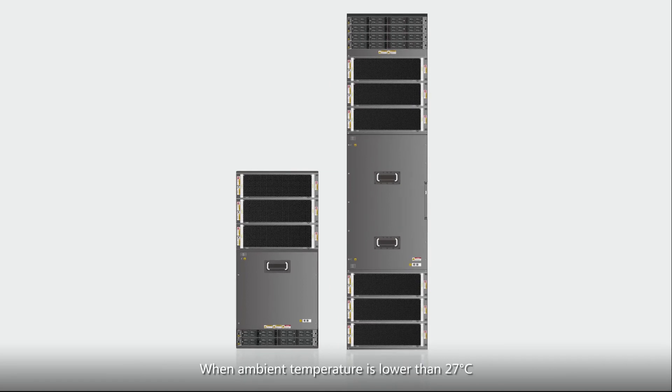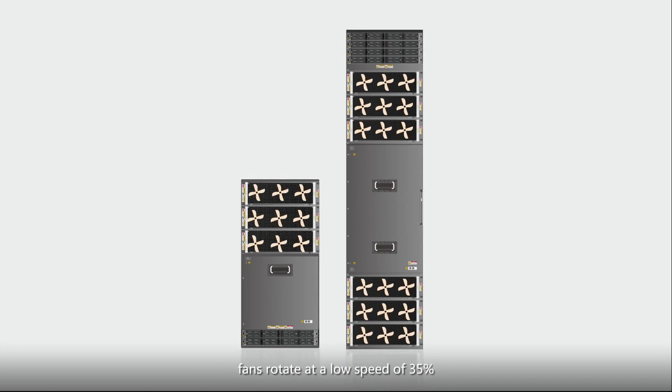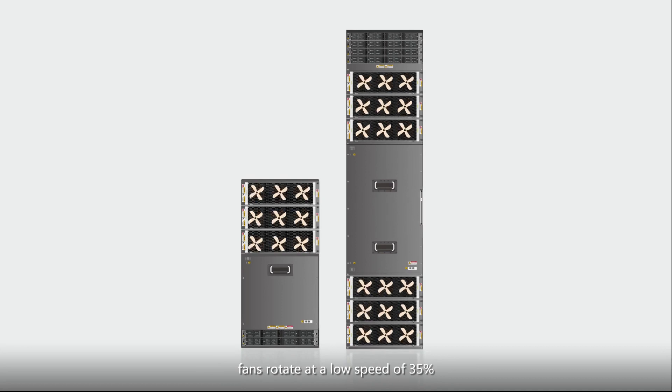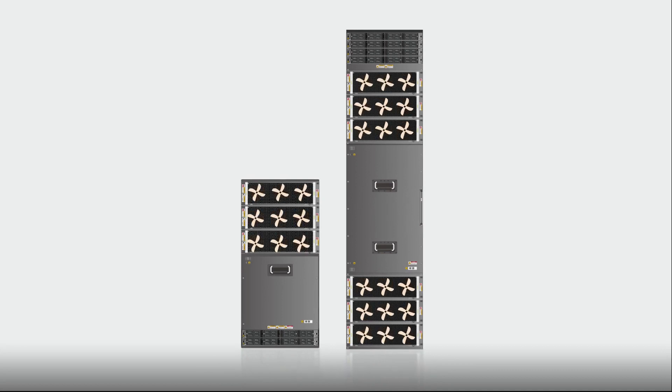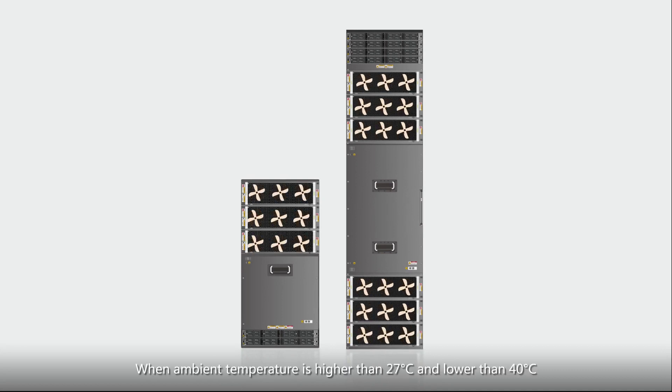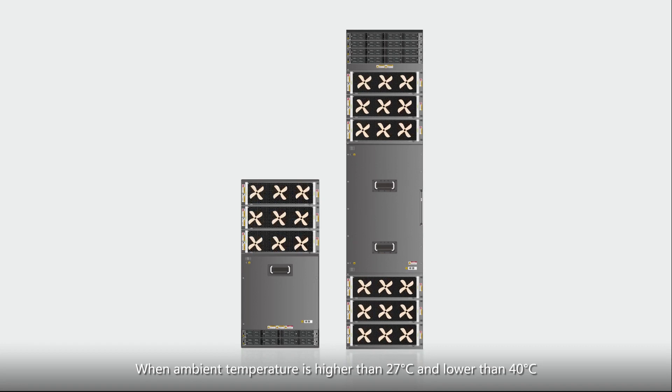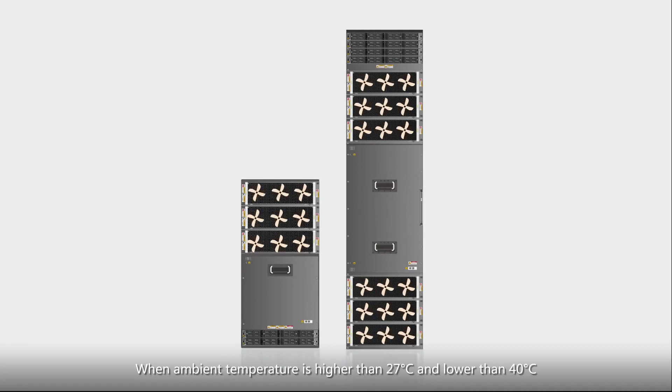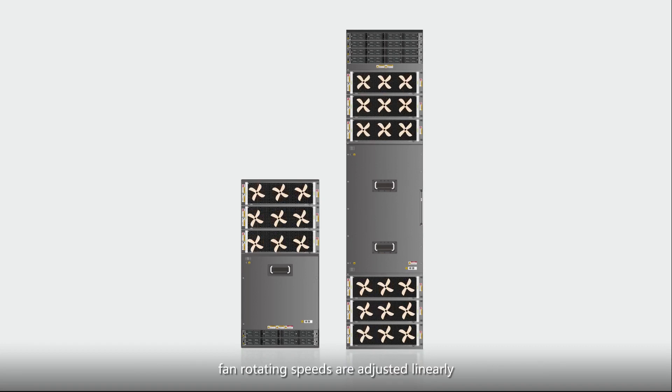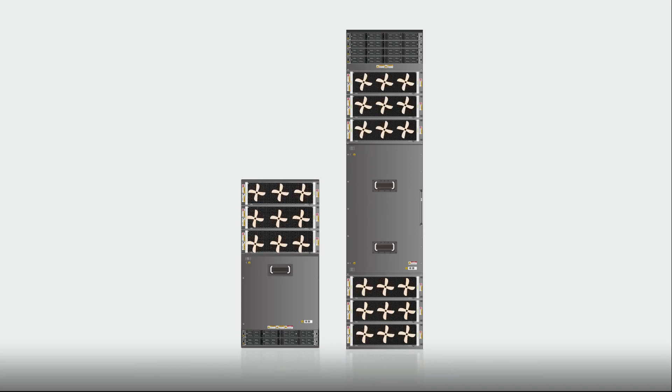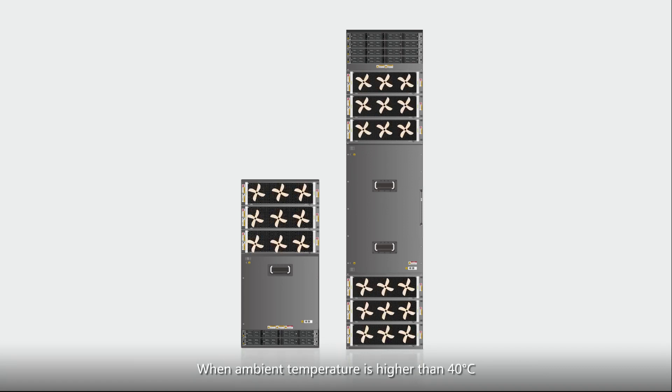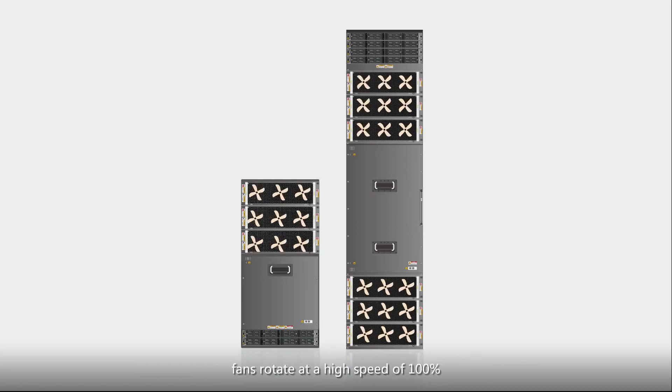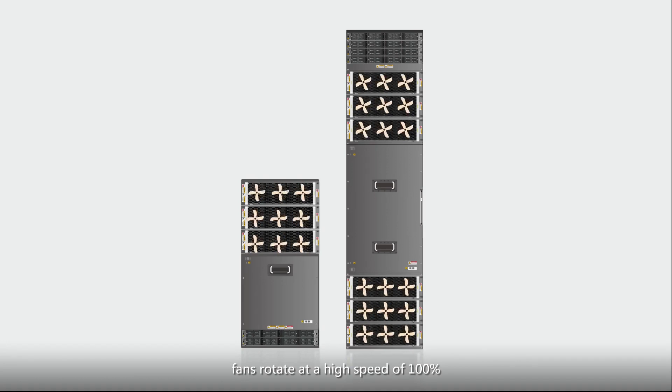When ambient temperature is lower than 27 degrees Celsius, fans rotate at a low speed of 35%. When ambient temperature is higher than 27 degrees Celsius and lower than 40 degrees Celsius, fan rotating speeds are adjusted linearly. When ambient temperature is higher than 40 degrees Celsius, fans rotate at a high speed of 100%.